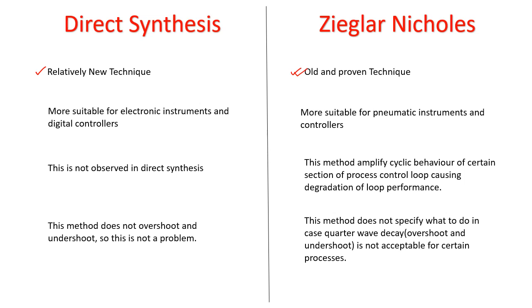In that time, the tuning was done by adjusting a screw. Transmission lines were pneumatic. Valves were not that precise, and these control loops needed a large surge of air pressure to overcome the line loss just to get the valve moving. So the Ziegler-Nichols technique worked great for this system.